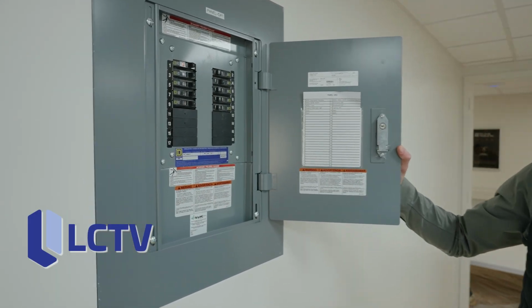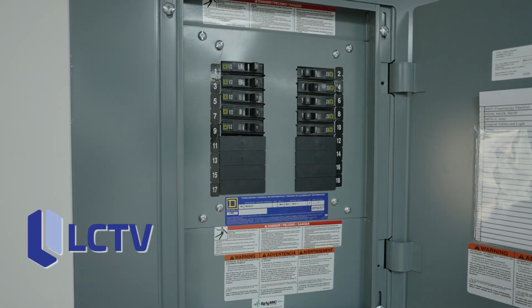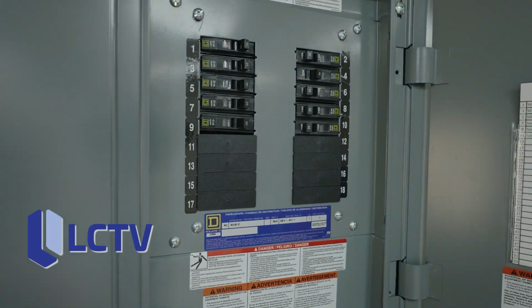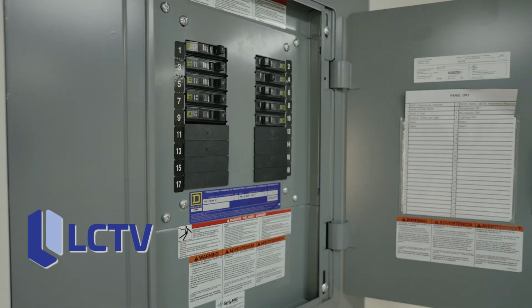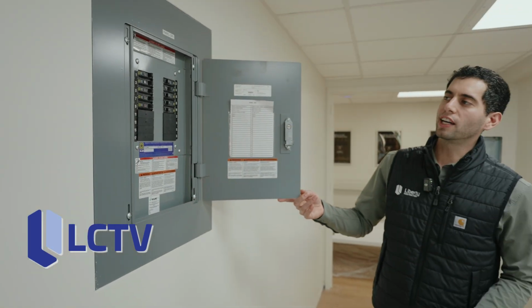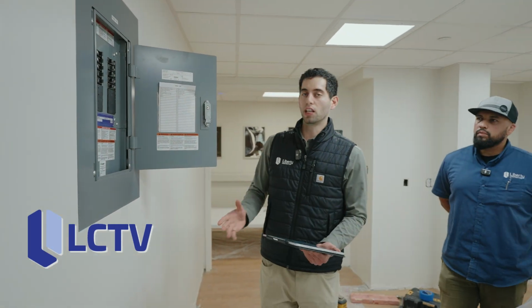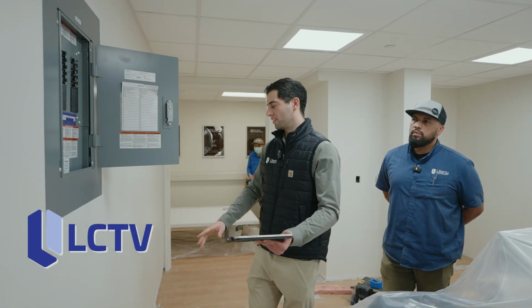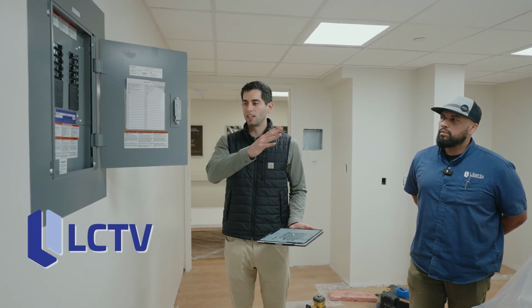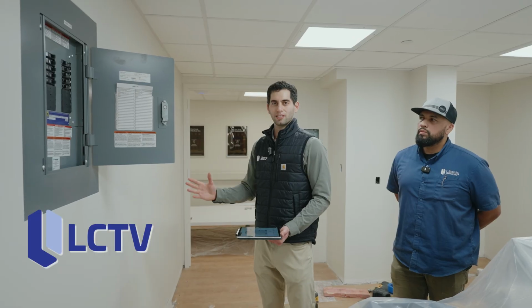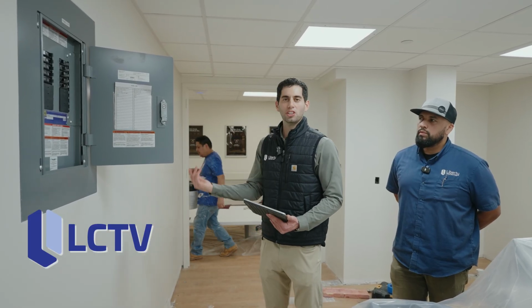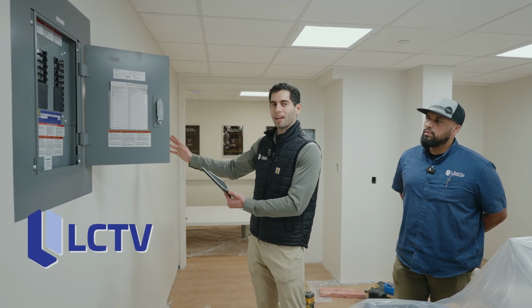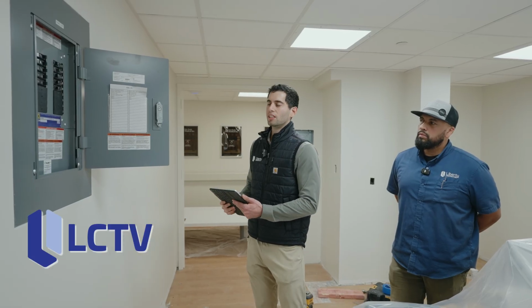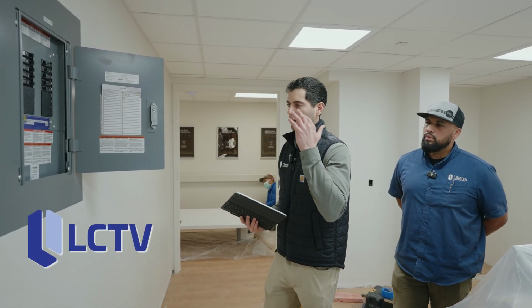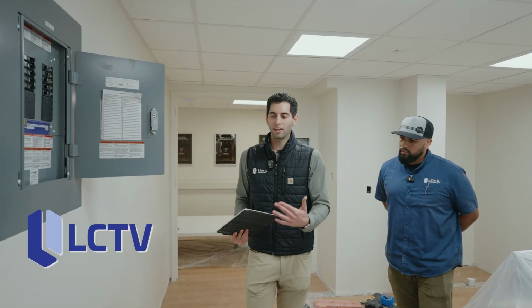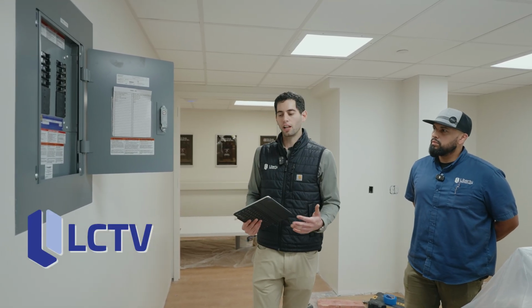So we have an 18 space, 120 panel, which should be healthcare grade. What makes an isolation panel different is it will isolate the circuits this panel feeds, so all the outlets and surgical light here, isolating it from the building's grounding. So if there's a voltage drop or power outage, even though we have UPS battery and a lot of redundancies in place, this is one more level that makes it close to impossible to ever have a shock or electrocution risk.